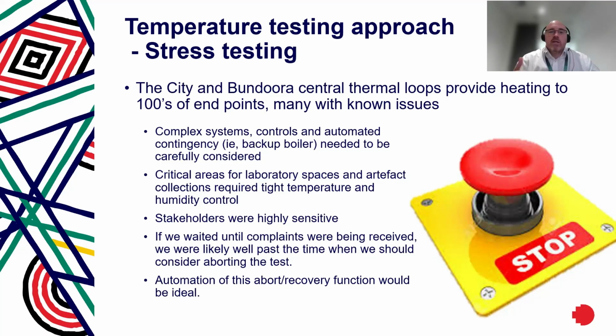So if we dropped the temperatures, we needed to monitor those actively and have automated recovery in the event things were going awry. We needed additional consideration for critical areas, labs, artifact collections like the archives. They had tight temperature and humidity control, so a heightened focus. I've already mentioned very highly sensitive stakeholders. It's our users, but also we had a number of test facilities that had even more sensitive conditions that were required.